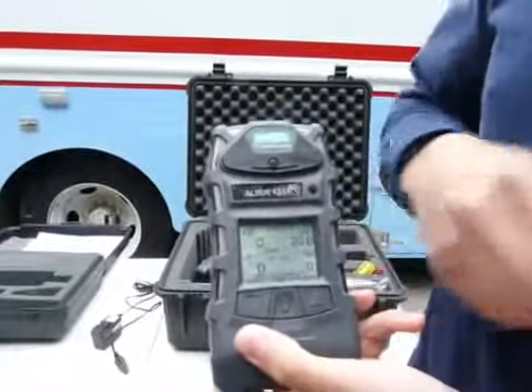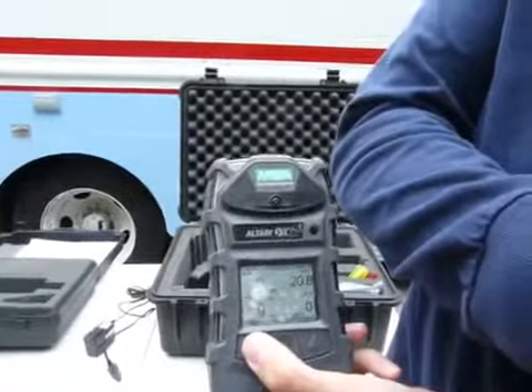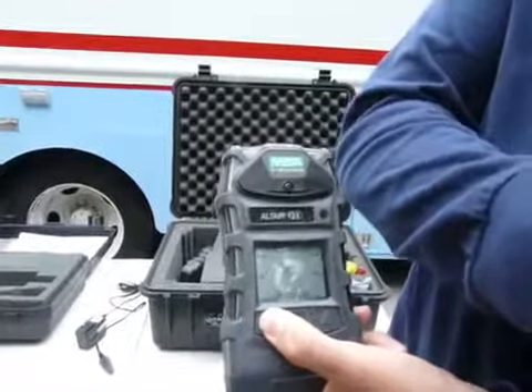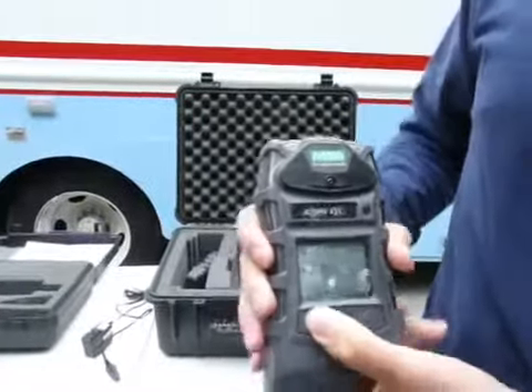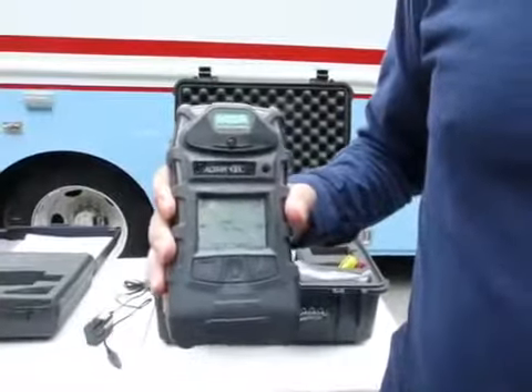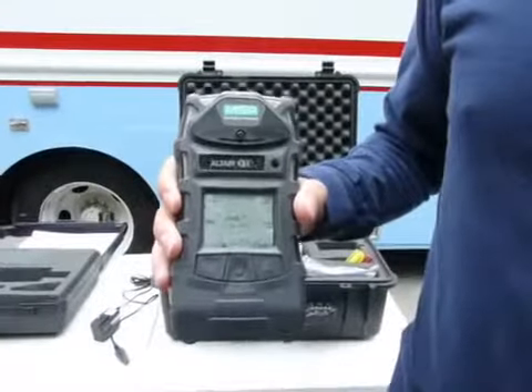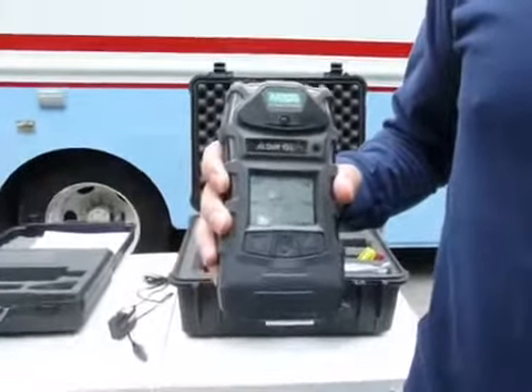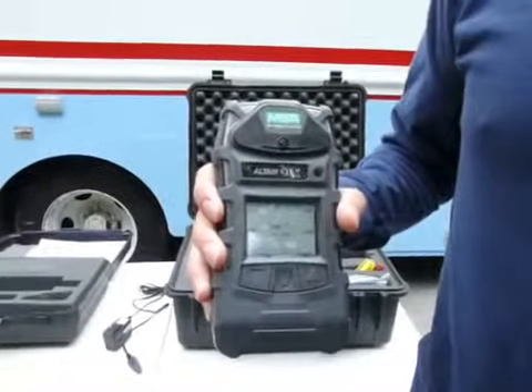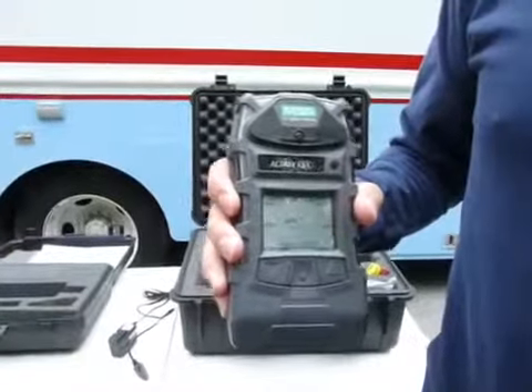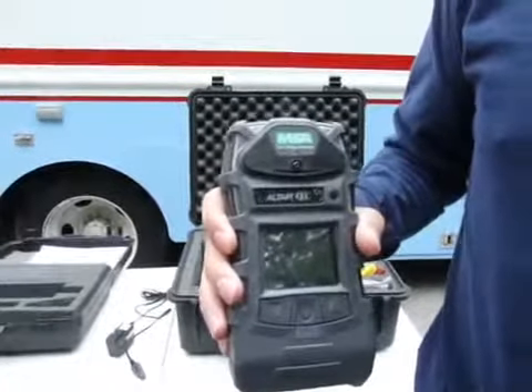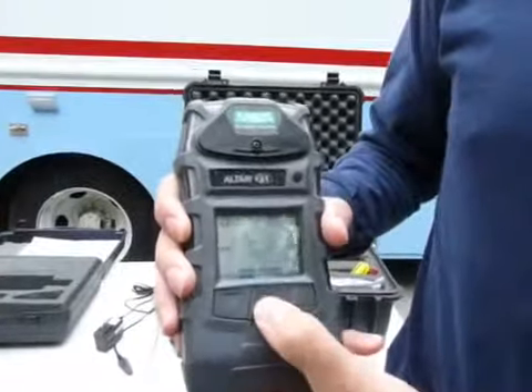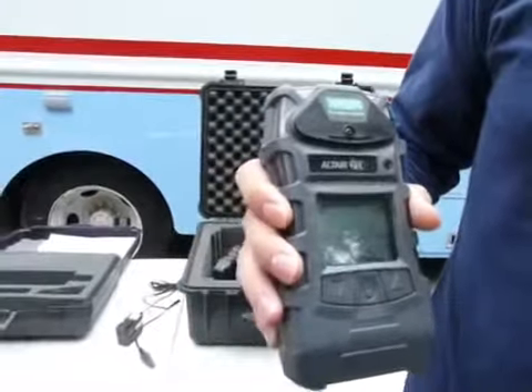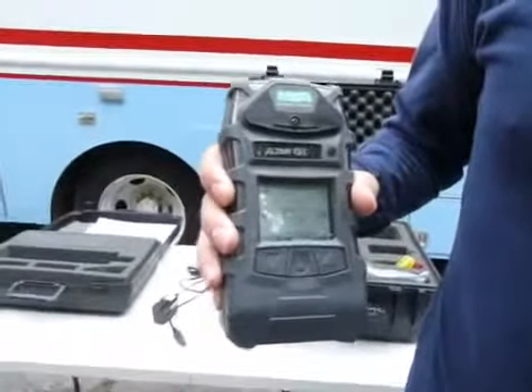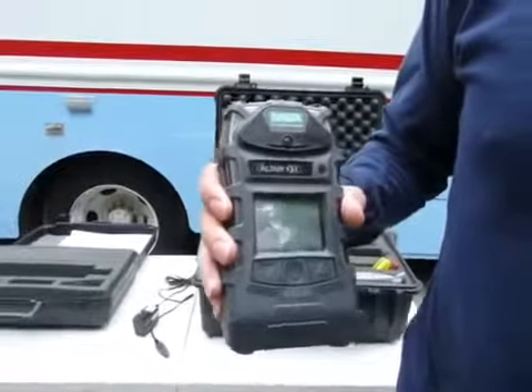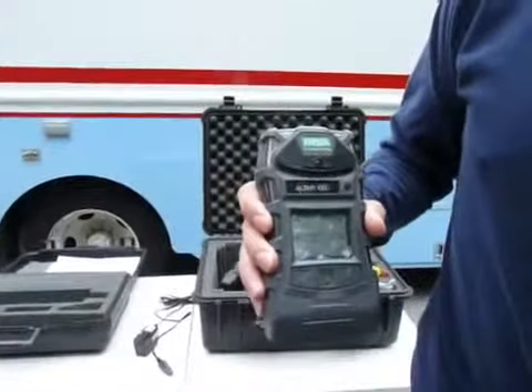First, it's going to ask if we want to zero out the calibration. So we're going to hit yes, which is the down arrow once, and it's going to zero out each of the sensors. For this portion, we want it to be in fresh air, away from any other sources of any of those four gases, so we certainly don't want to be near any vehicles, because vehicle exhaust can change the values that we might expect. And this takes about 45 seconds to a minute to complete, so you do have to give it a little bit of time.